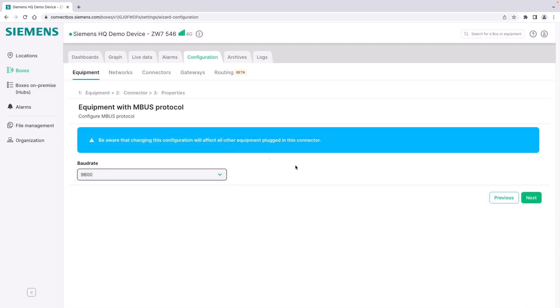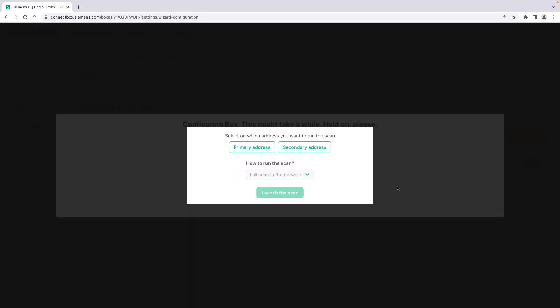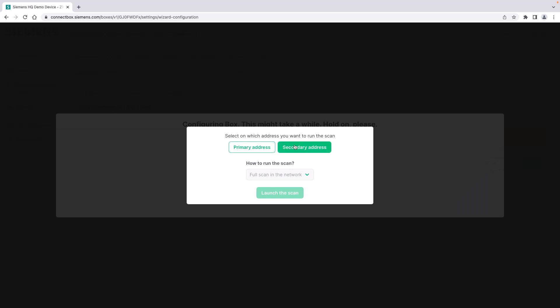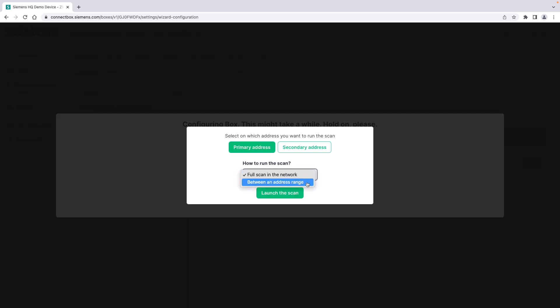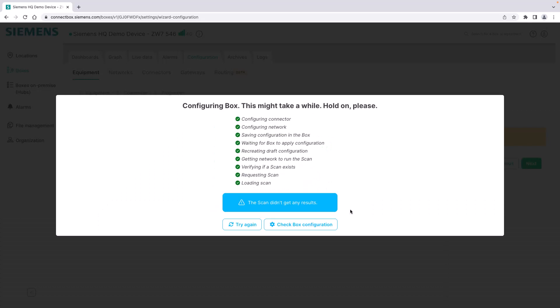You select here the baud rate of your network in case you haven't configured that before or want to change it here. You click next and the box is automatically performing a network scan. You can also define if you would like to run the scan based on the primary or the secondary address and a full scan or in between an address range. We can launch the scan. Since we don't have any M-Bus devices connected, the scan didn't get any results and couldn't find the device.